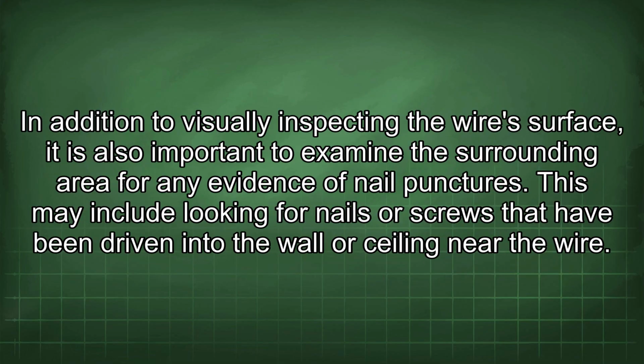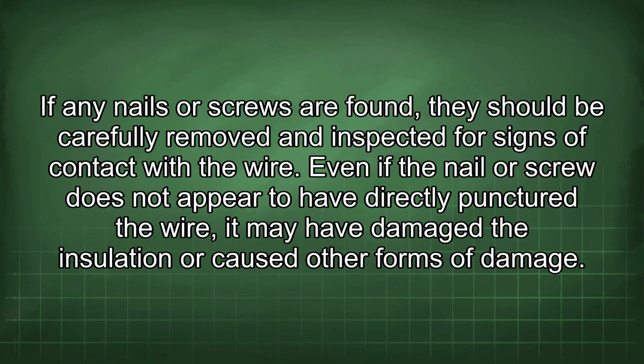In addition to visually inspecting the wire's surface, it is also important to examine the surrounding area for any evidence of nail punctures. This may include looking for nails or screws that have been driven into the wall or ceiling near the wire. If any nails or screws are found, they should be carefully removed and inspected for signs of contact with the wire. Even if the nail or screw does not appear to have directly punctured the wire, it may have damaged the insulation or caused other forms of damage.